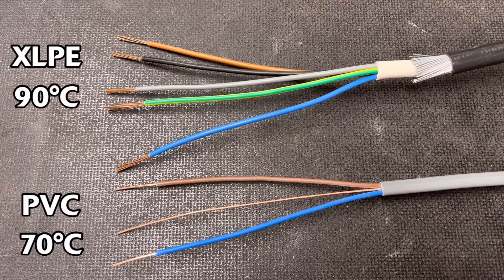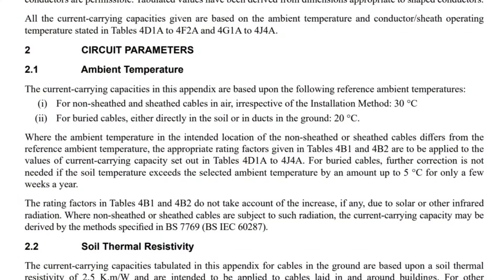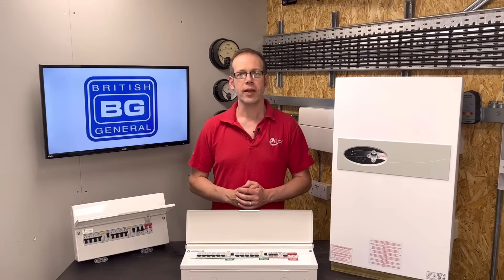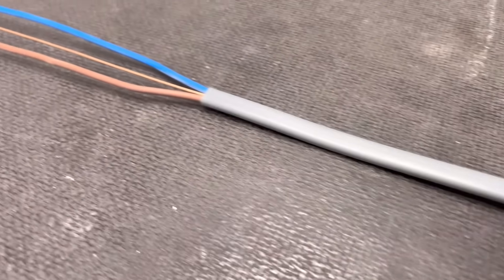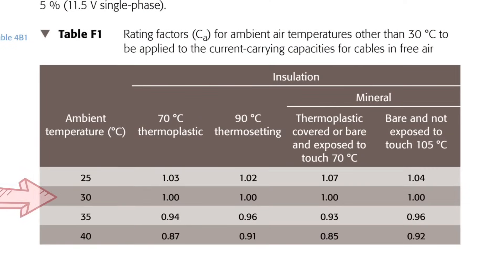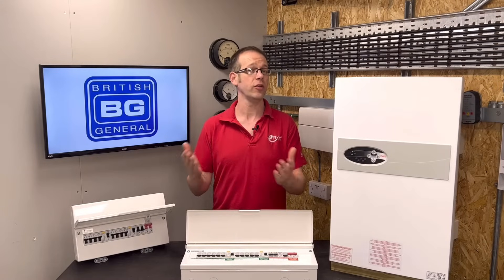Then you've got 90 degrees C thermosetting, which is what you'd find on XLPE insulated steel wire armoured cable. The final two columns relate to mineral insulated cables, which have become pretty uncommon except in specialist installations. So let's assume we're going to wire our electric boiler in twin and CPC cable with 70 degrees C thermoplastic insulation. If the ambient temperature in the installation is 30 degrees C, the rating factor will be one. This is significant because it means a temperature of 30 degrees C will not affect the current carrying capacity of the cable — dividing by one doesn't change its value.